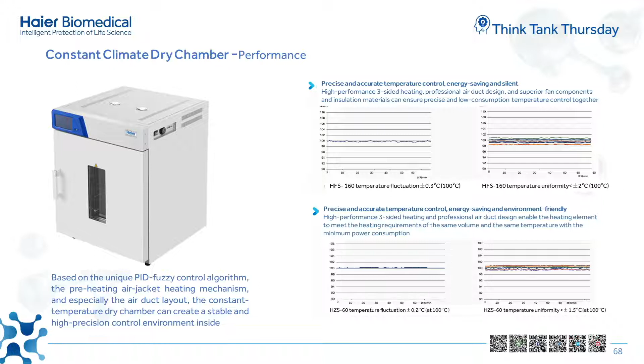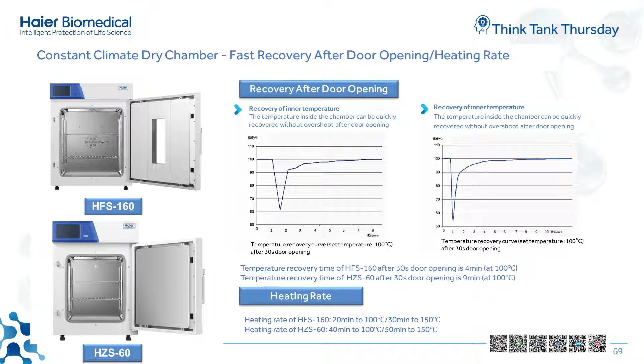Secondly, the recovery time after door opening is quite short. After 30 seconds from opening the door, the HFS160 only needs 4 minutes to recover to 100 degrees Celsius, and HZS-60 needs 9 minutes. The heating rates of both models are also high. Thirdly, the convenient and user-friendly smart operation of the instrument greatly improves the efficiency in the labs. The 4 modes can satisfy the different requirements and the lab shifts for laboratory staff working time as well as temperature changes by using the setting functions and self-programmed setup.